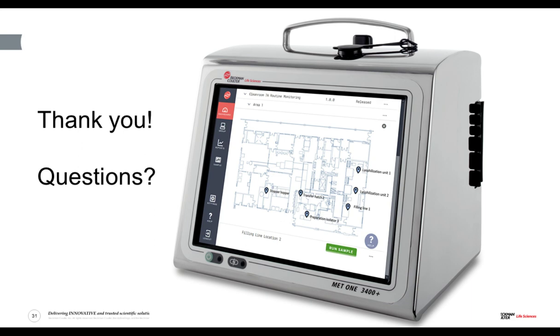Your next question: you showed a remote review and approve feature for the MET ONE. What software is required to access the counter remotely, and how do you guarantee security? In fact, you don't need any software to access the counter remotely. As long as the counter is connected to your company network, you can control SOP versions and review and approve data from your office simply using a web browser such as Google Chrome. Security is assured as the user who logs on remotely must use their Microsoft Active Directory controlled username and password via the web browser interface.